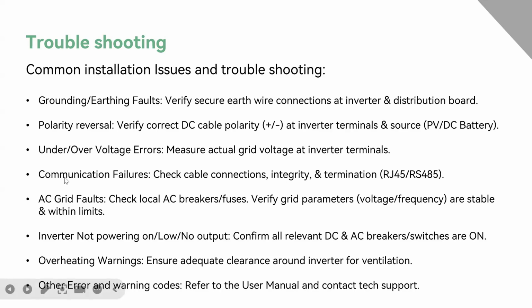As for communication failures, which commonly happen with the battery or in a parallel system, we have to check the cable connections, the integrity, and the terminations. Also check if we have chosen the right battery brand. And as for AC grid faults, we have to check the local AC breakers or the fuses and verify the grid parameters are stable and within limits.